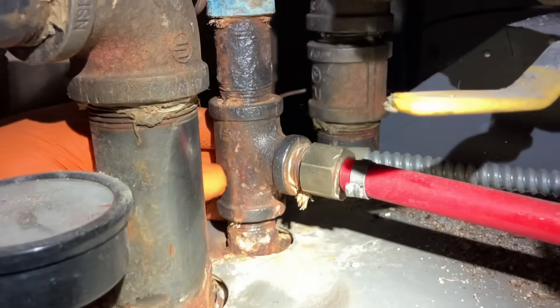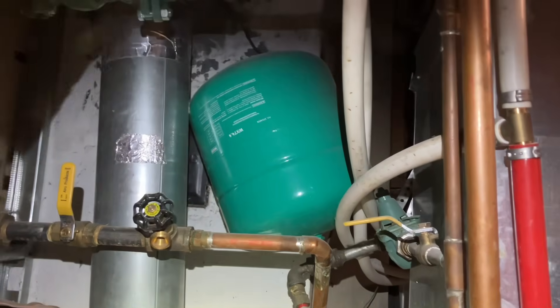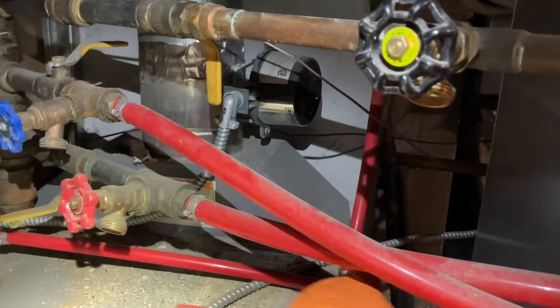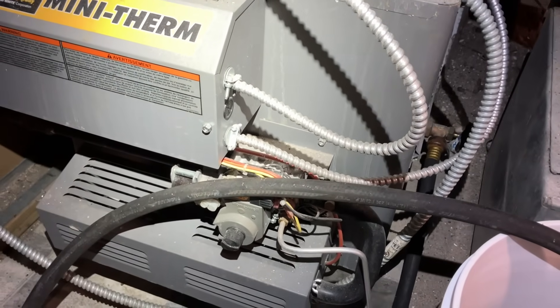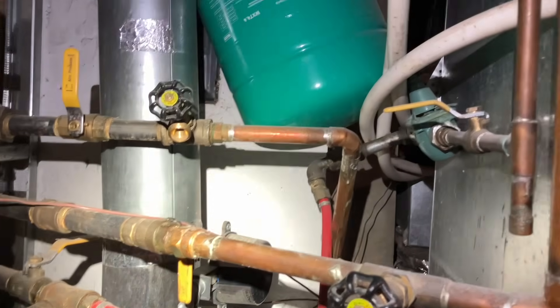Using those metal brushes I confirmed there's just a lot of superficial corrosion on the black T and the nipple — it's pretty solid. I'm going to change this nipple and the relief valve. I still haven't figured out how I'm going to do this, but ideally if I could orientate the tank in a vertical position facing downward, that would be preferred. I'd have to reconfigure the piping — ideally go across with a piece of half-inch black pipe, put a T here, hang the tank, though it's still kind of in the way of the gas control valve. This is not on the budget.